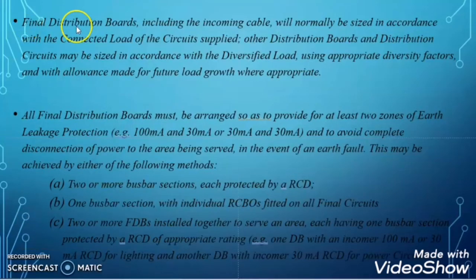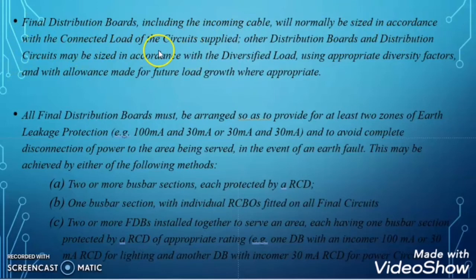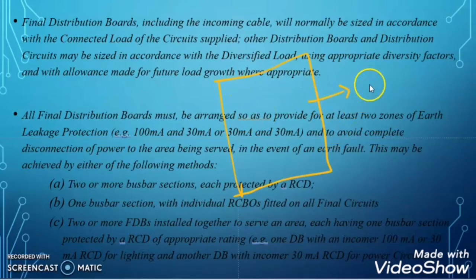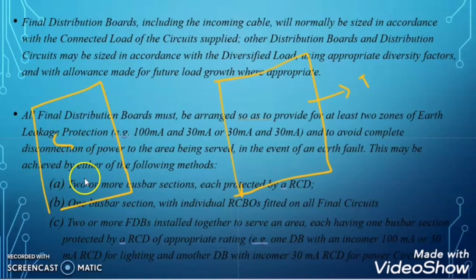The first ADDC clause states: final distribution boards including the incoming cables will normally be sized in accordance with the connected load of the circuit supplied. Other distribution boards and distribution circuits may be sized in accordance with the diversified load using an approximate diversity factor, with allowance made for future load growth where appropriate. In short, the FDB is designed based on the total connected load, while the SMDB and MDB are designed based on the diversified load.